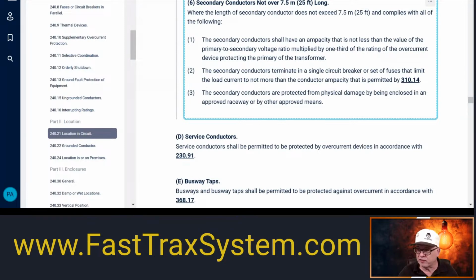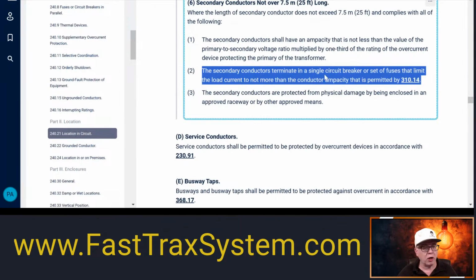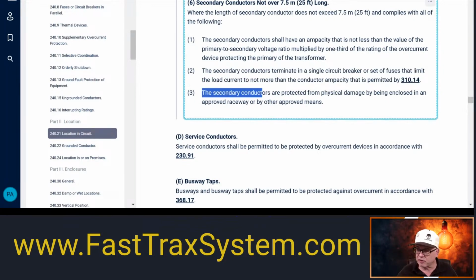Okay, well, then it says a conductor, okay? We can't have the circuit breaker. It has to protect the load, and not more than the conductor's ampacity. So if we're going to have 200 amps, then we need to increase that conductor's size. So this ends up being a minimum. And then, of course, we have to be aware of these rules, depending on what load we're trying to serve in that panel.